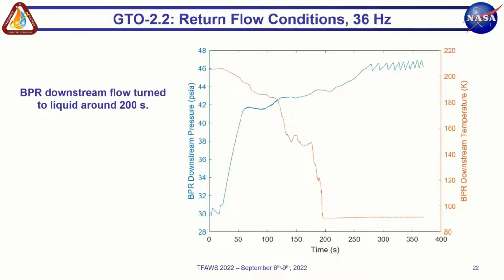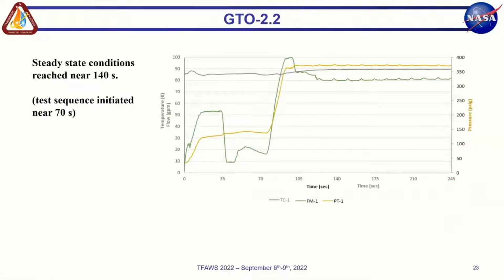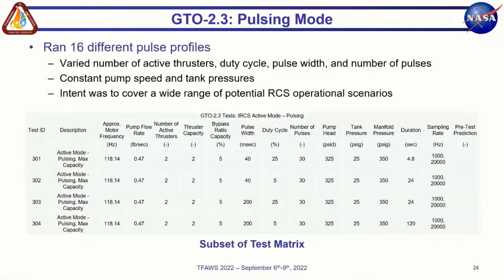We could first of all see that if we just started firing, we didn't really get into actual chilled in steady state conditions until about 200 seconds into running the test. For this next test sequence, we initiated the test sequence at 70 seconds, and then everything steadied out at 140. So this one only took about 70 seconds to reach steady flow conditions.